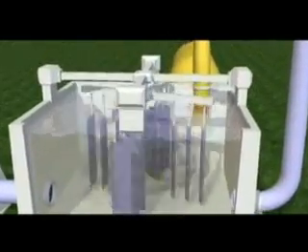and bacteria. We add a precisely controlled amount of a coagulant like ferric or aluminium sulfate. This reacts with the material in water, making it all stick together to form what's known as floc. To make this flocculation happen, water and the coagulant have to be mixed together very quickly and thoroughly in a special device called a flash mixer.